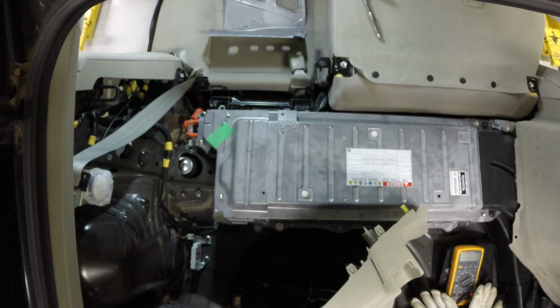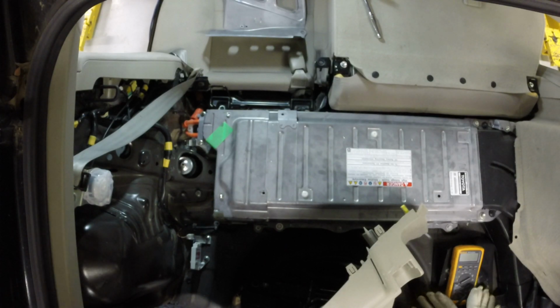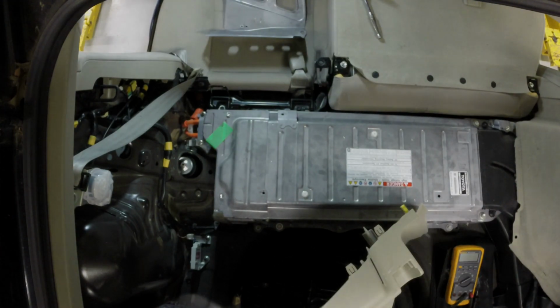So again, minimizing risk, we want to make sure we're not producing a scenario where we could potentially get shocked by a panel falling on a terminal or something of that nature, and getting to the point where we sustain an arc. So I'm going to get these last few bolts out for this under panel, and we're going to go ahead and throw our gloves on and do the rest.